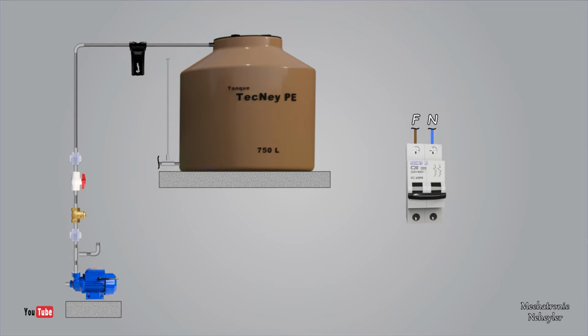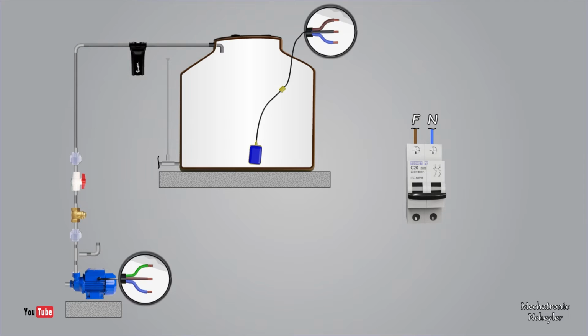Now, let's look at the simplest connection that can be made using an electric float in an elevated tank. First, the minimum and maximum level at which the electric float will operate must be regulated. To do this, the distance from the counterweight to the head of the float and the height at which this counterweight must be fixed in the tank must be adjusted.